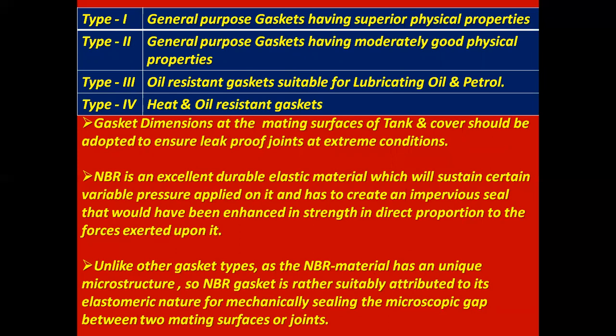Gasket dimensions at the mating surfaces of tank and cover should be adapted to ensure leak-proof joints at extreme conditions. NBR is an excellent durable elastic material which will sustain certain variable pressure applied on it and has to create an impervious seal that would be enhanced to strengthen in direct proportion to the force exerted upon it. Unlike other gasket types, as the NBR material has a unique microstructure, NBR gasket is rather suitably attributed to its elastomeric nature for mechanically sealing the microscopic gap between two mating surfaces or joints.